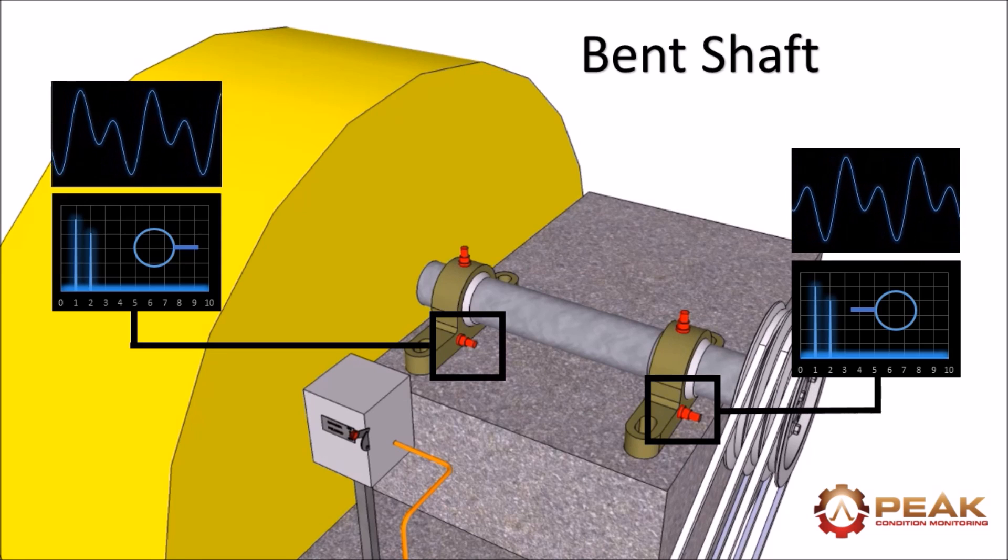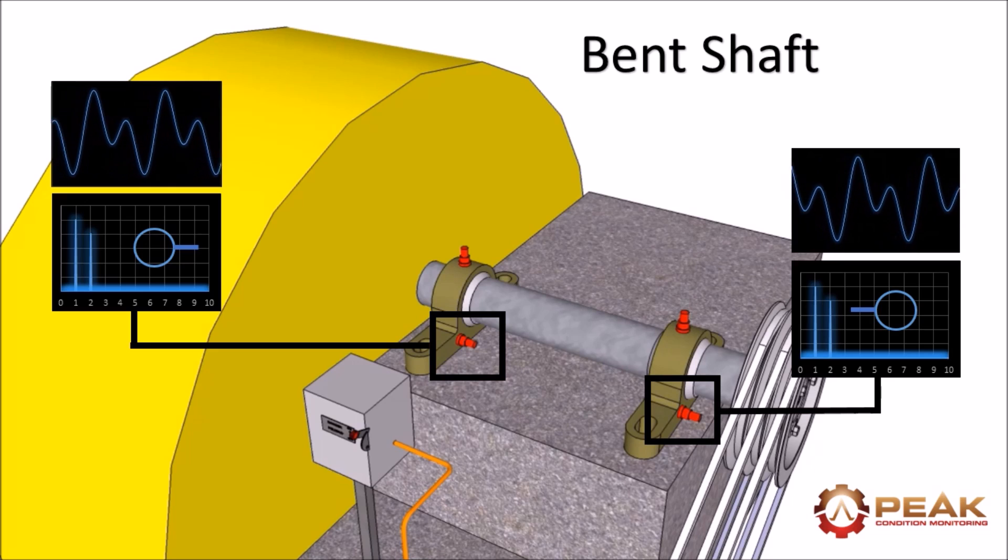If the phase of the two waveforms is out by 180 degrees then the problem is caused by a bent shaft.